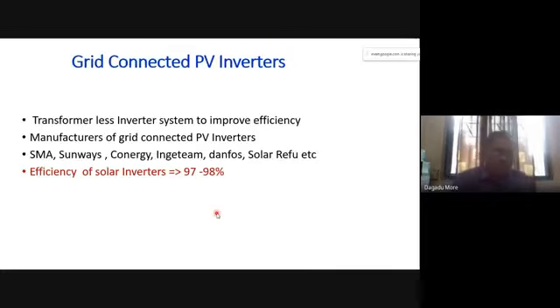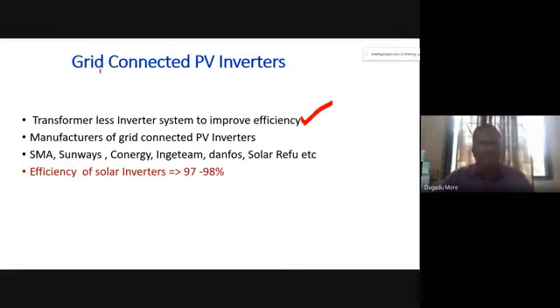And now we want to avoid the transformer. The intention to avoid the transformer is to improve the efficiency and reduce the cost of the system. So in grid connected PV inverters, we are not using a power transformer for isolation between the PV system and the grid. The sole purpose is to reduce the cost and improve the efficiency.